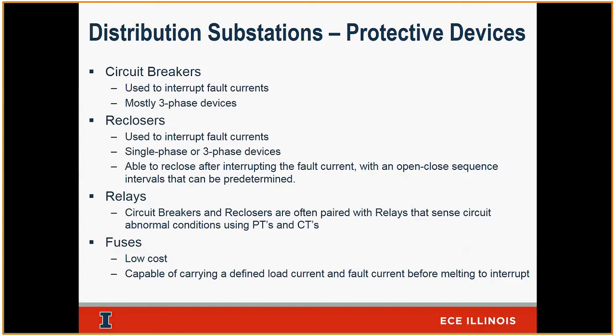Current on a typical distribution feeder like this could be 200 amps, 250 on hot days. That's the amount of amps you're providing to your load. So the customers, as they turn lights on and off, fridges are on, all that equipment is drawing current. The totality of that on one feeder could be around 200, 300 on average for our feeders. When there's a fault, when there's an abnormal condition that happens, so two phases touch, right?